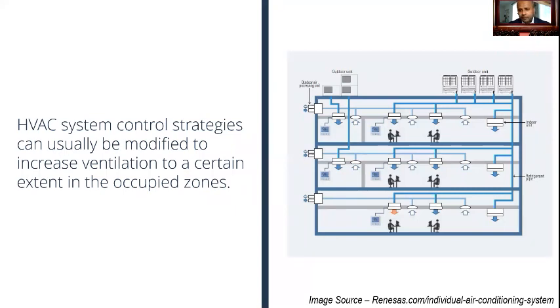In a mechanically ventilated building, ventilation air is typically provided by an HVAC system. Sometimes ventilation air is provided by dedicated fans or outdoor air units. For homes with window air conditioners, for places like New York, you have to operate your window AC with the outdoor air intake. For commercial offices and centrally air conditioned spaces, your facility manager or building manager or super can usually modify the controls to increase ventilation to a certain extent in the occupied zones without an additional cost.